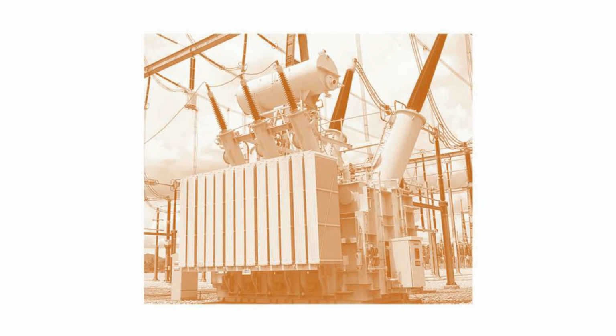Let's talk about yearly maintenance now. The first thing we should look at is the oil condition inside the on-load tap changer. The transformer bushings should be cleaned and checked for cracks as well. We should also check all alarms, relays, and controls related to the transformer to see if they are functioning correctly. Then we need to check the pressure relief device and the Buchholz relay to make sure that they can operate if needed.